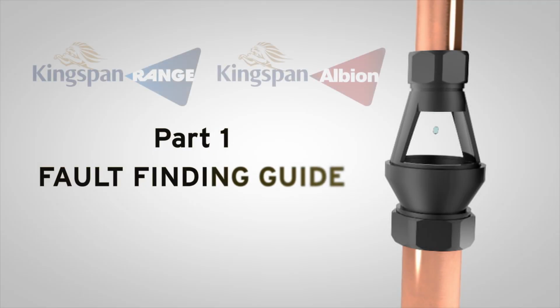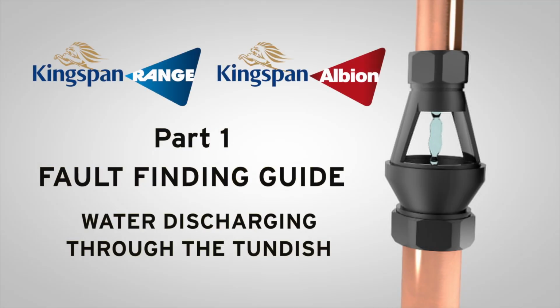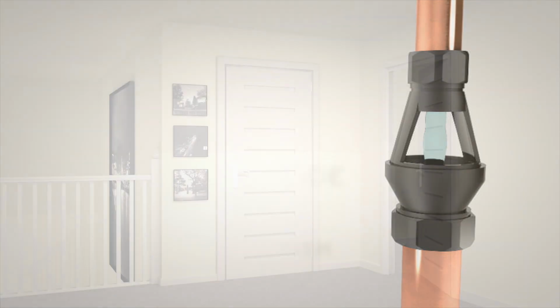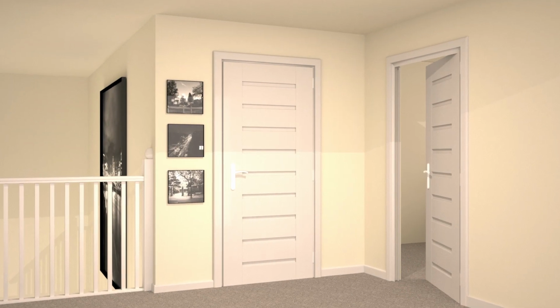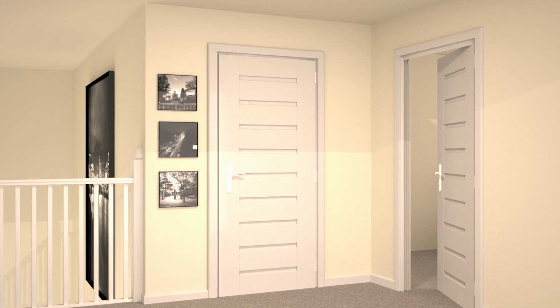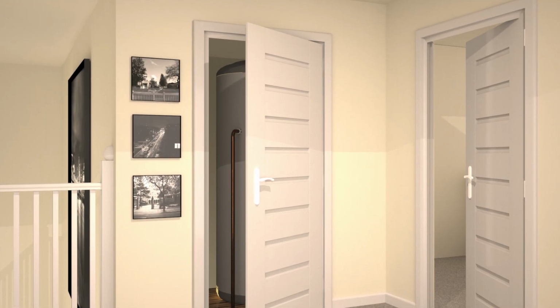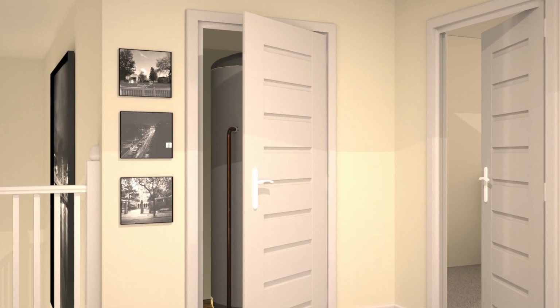Fault Finding Guide, Water Discharging Through the Tundish. Welcome to part one of this fault finding guide, showing installers how to diagnose the cause of water discharging through the Tundish. The Tundish is a key component designed so that homeowners can detect the presence of a fault within their heating system. In normal operation, water will not discharge through the Tundish.